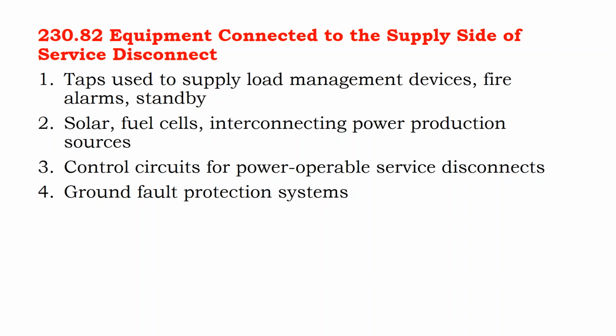And so maybe your local solar rebate program has only been doing load side interconnections because your local solar rebate program is being run by non-electricians and they're just copying off each other's homework and passing this load side connection requirement down the ranks. By the time solar gets to your local building permit office, the electrician assumes the solar program, who knows more about solar technology than they do, knows what they're doing.